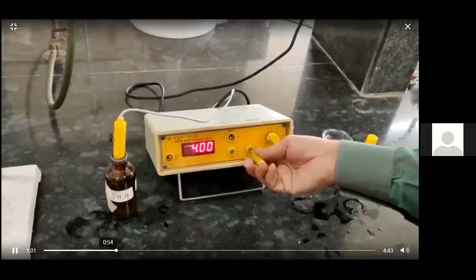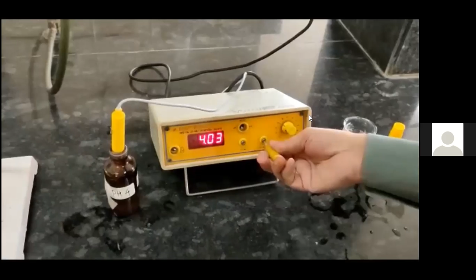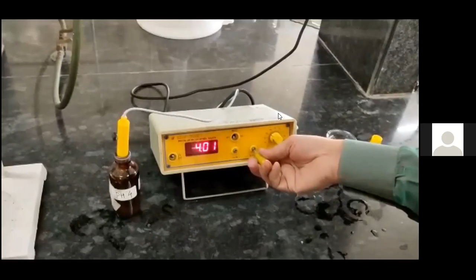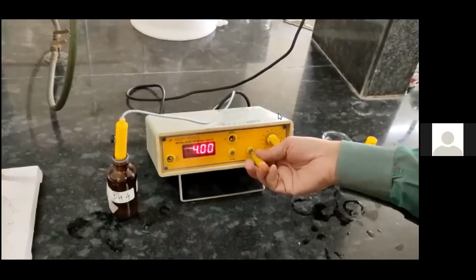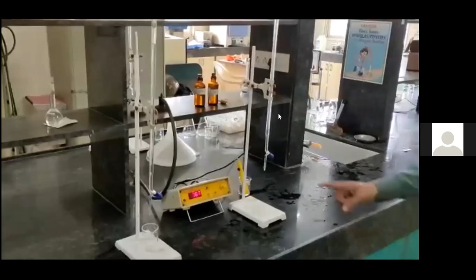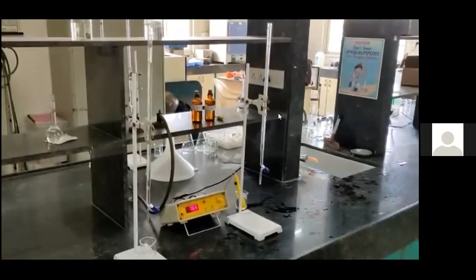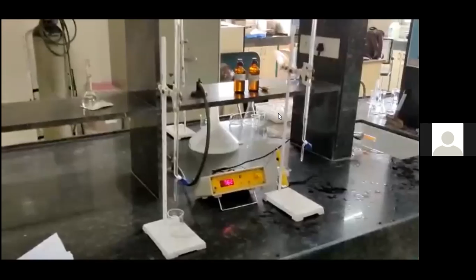The standardization part. Here this is a slope knob and this is the asymmetric knob. We have dipped the electrode in the pH 7 and with the help of a screwdriver we have made the pH meter read 7. Then this is another buffer having 4. With the help of a screwdriver we have adjusted the pH manually to 4, and one more we have to do with 9, so that your pH meter gives reproducible readings in the acidic range, neutral range as well as alkaline range, and that is called standardization.